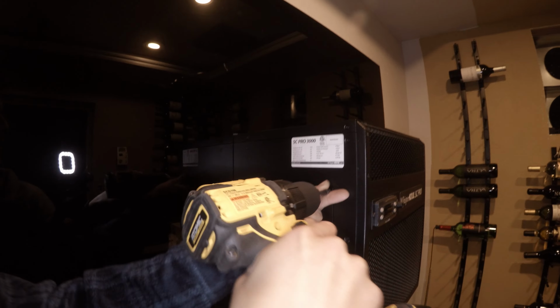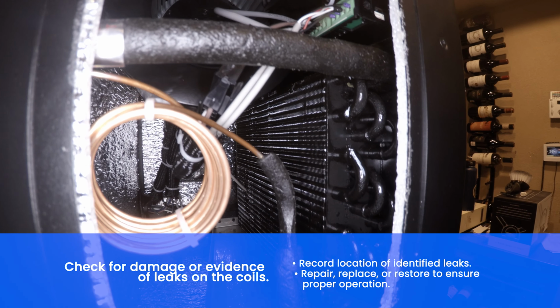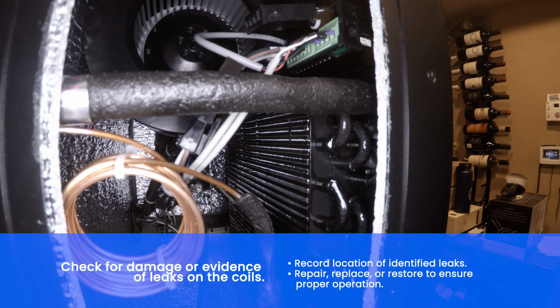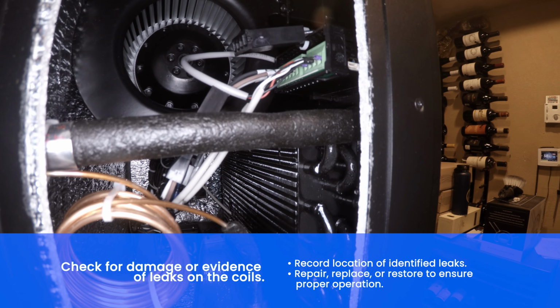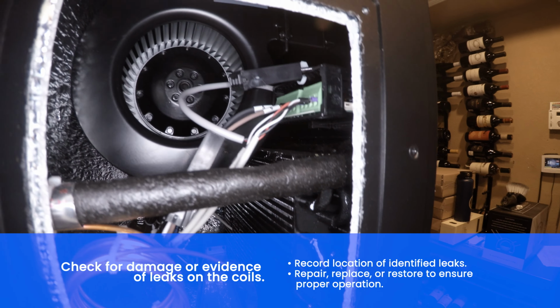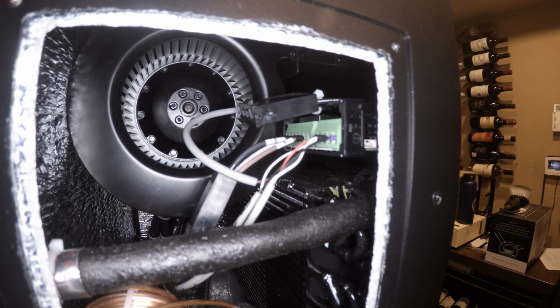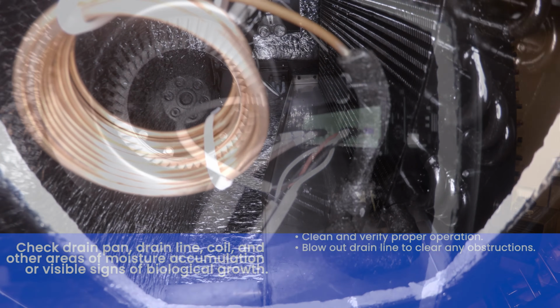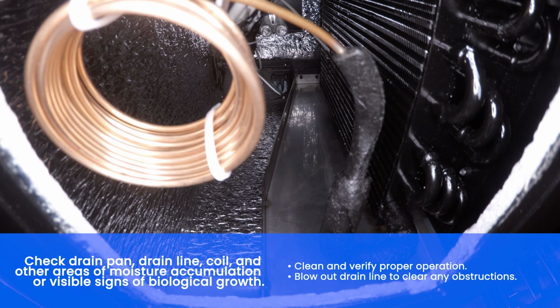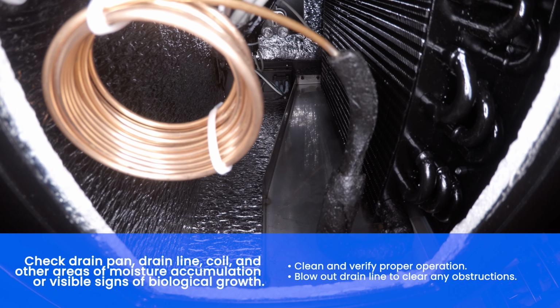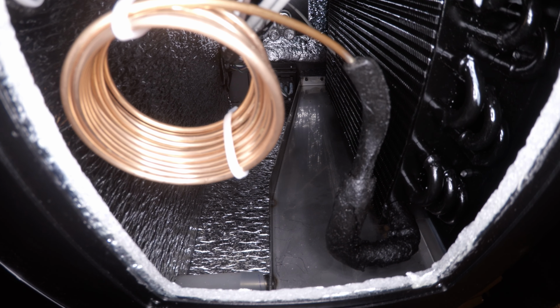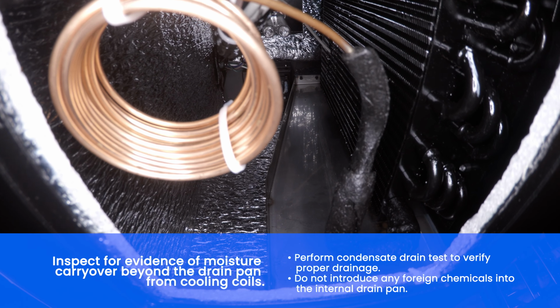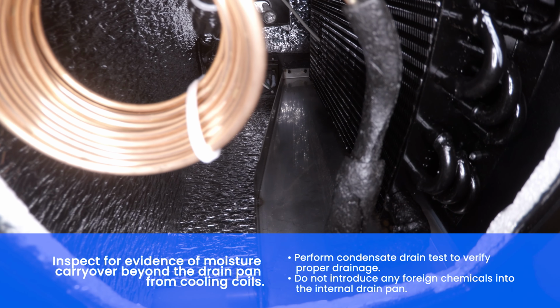Remove the 4 screws and access panel from the side of the unit. Check for damage or evidence of leaks on the coil. Check the drain pan, drain line, coil, and other areas of moisture accumulation for visible signs of biological growth. Inspect for evidence of moisture carryover beyond the drain pan from the cooling coil.